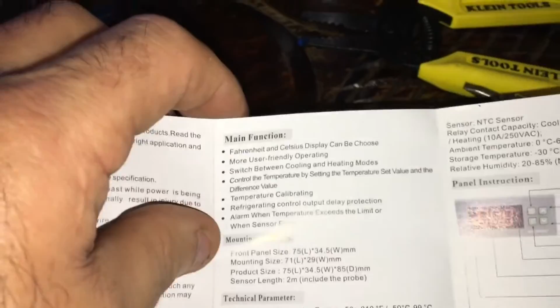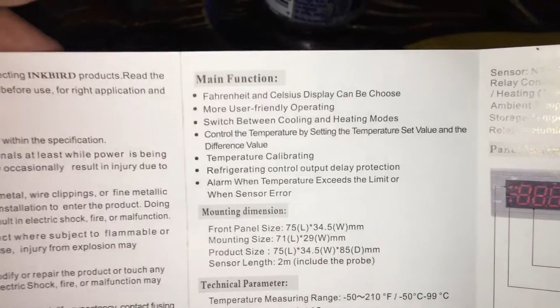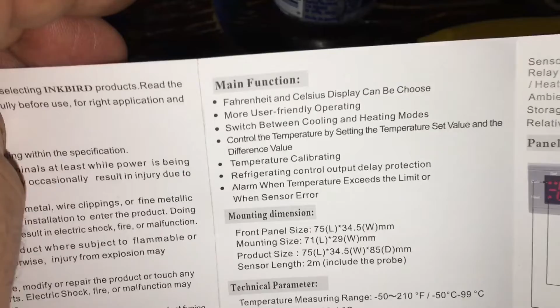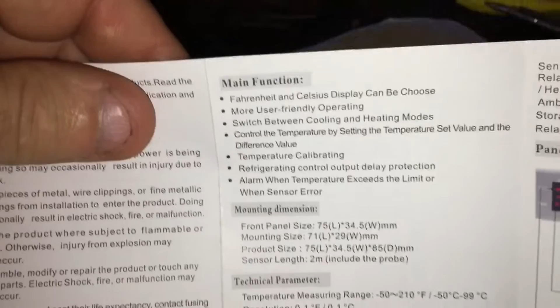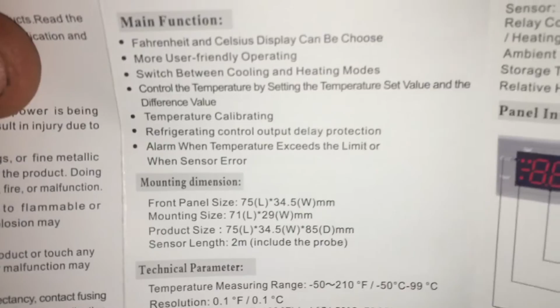For this is made in China, so the English is going to be a little different. Switching between cooling and heating modes. Control the temperature by setting temperature set value and the difference value. It also has refrigerating control output delay, which is mandatory for me. I always have to do a 5-minute compressor time delay. Everything I do always has a minimum of a 5-minute time delay. Whenever a compressor goes off, I never let it come back on unless for 5 minutes.